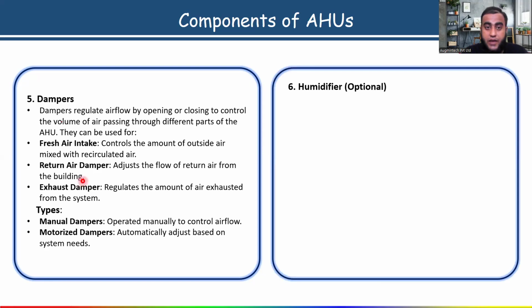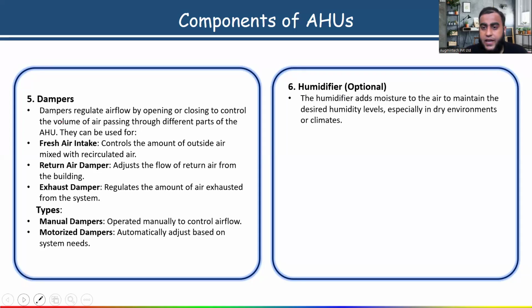Then we have a humidifier. It is optional. As I told you, let me know, all of you, for what situation we have to use it. As I already explained in the beginning, a humidifier is a device which adds moisture to the air in the AHU, the air handling unit. For human comfort, we have to maintain 50% relative humidity. Suppose for a location you are designing where the humidity level is low, to maintain 50% humidity we have to install a humidifier. That is why it is given, and it is optional. I will explain how to select the humidifier here. Its main purpose is to add moisture to the air to maintain the desired humidity level, especially in dry environments or climates.